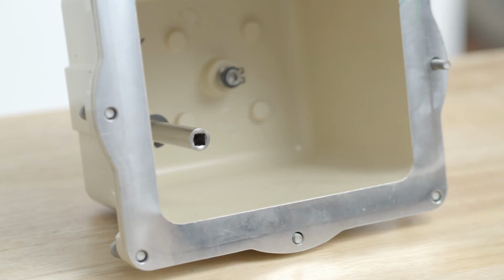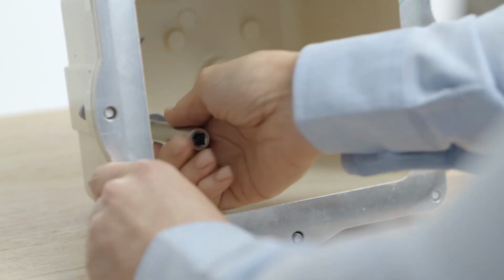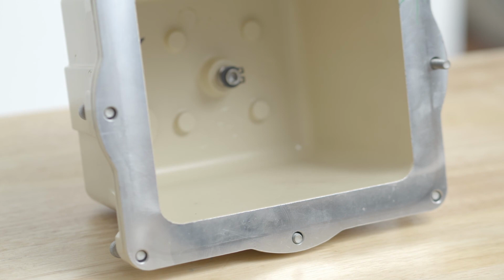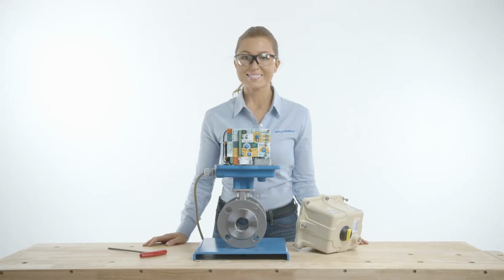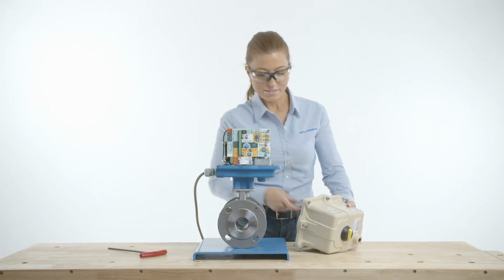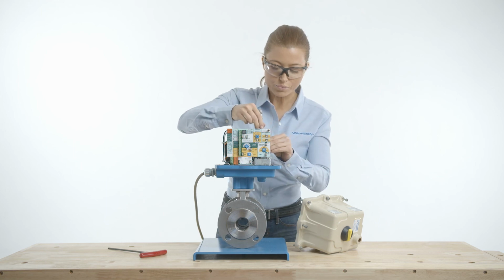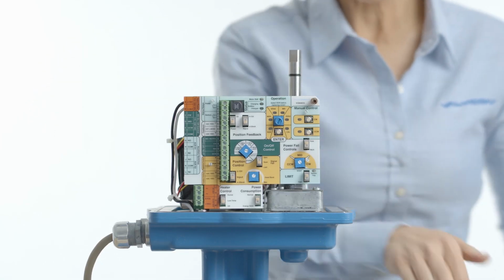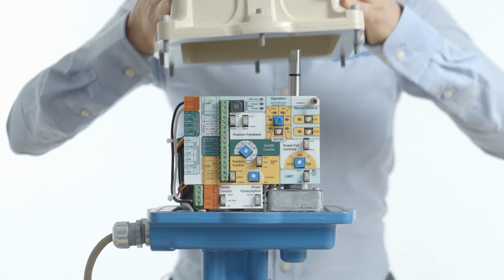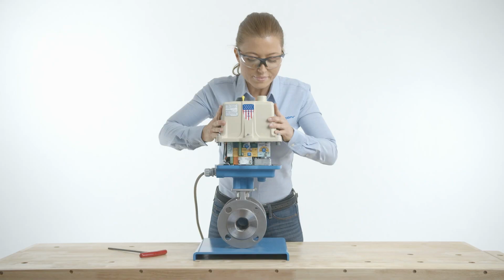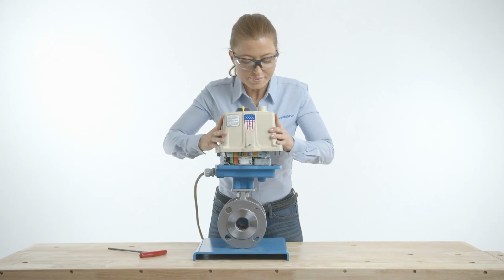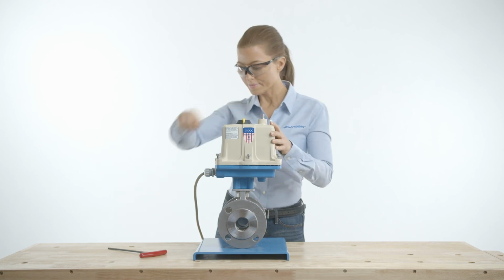To properly replace the actuator cover, remove the override shaft from the actuator cover bushing. If the actuator is equipped with a hand wheel, remove the hand wheel before removing the top piece of the two-piece shaft from the cover bushing. Install the override shaft on the square motor shaft. If equipped with a hand wheel, install the bottom piece of the two-piece shaft on the motor shaft, and then install the top piece of the shaft onto the bottom piece of the shaft.